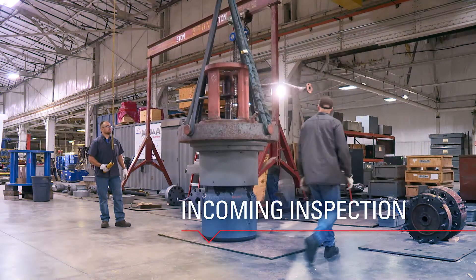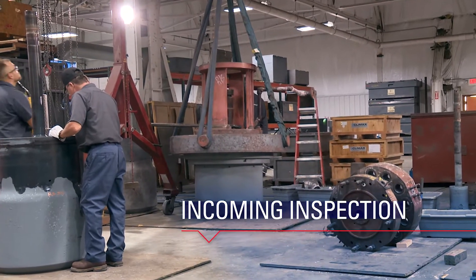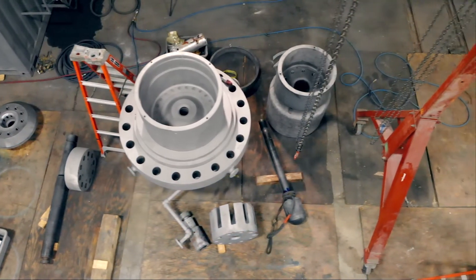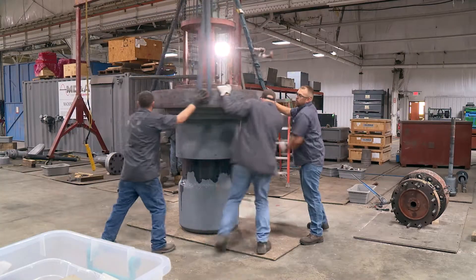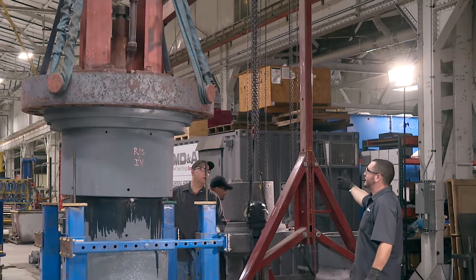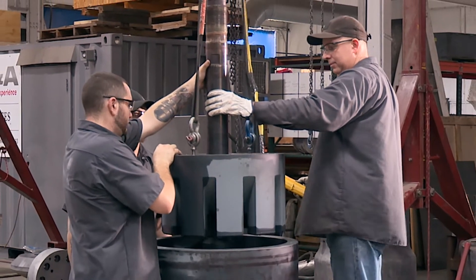After the valves arrive from the customer site, we begin with disassembly. We perform an incoming inspection of all valve components and detailed dimensional checks on standard MD&A forms. A complete report including those forms, NDE reports, and photographs along with repair recommendations are provided to the client prior to any repair.